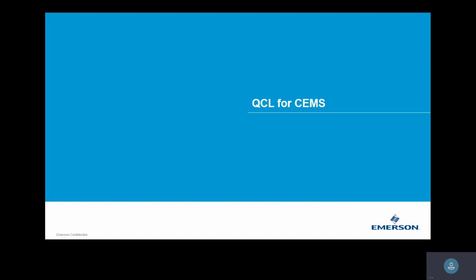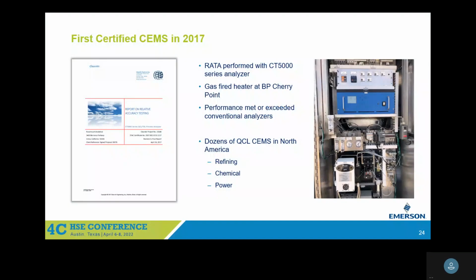So how have we been doing with this with CEMS? Our first CEMS that we went through and passed RATA was in 2017 with these. I can publicize that because Cherry Point did a joint paper with us about that. It was their first one, so they did a 50-day stability test as opposed to 7 days, and it really performed very well. It met or exceeded conventional analyzers. They never had to do any calibrations during that time with our system.